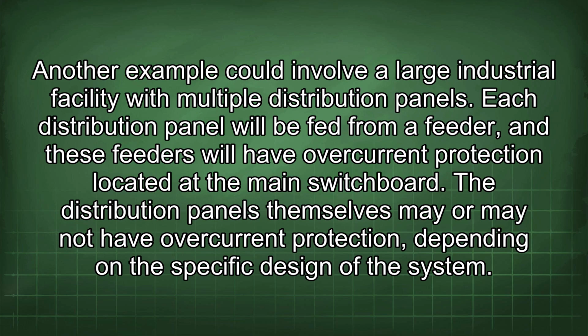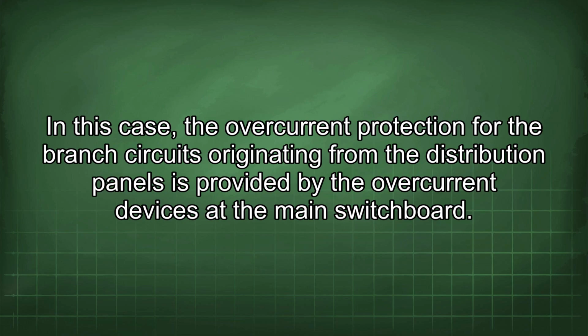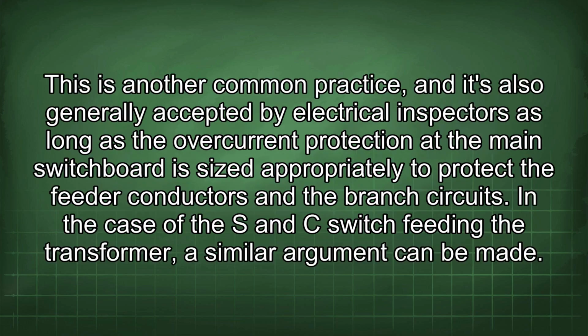Another example could involve a large industrial facility with multiple distribution panels. Each distribution panel will be fed from a feeder, and these feeders will have overcurrent protection located at the main switchboard. The distribution panels themselves may or may not have overcurrent protection, depending on the specific design of the system. In this case, the overcurrent protection for the branch circuits originating from the distribution panels is provided by the overcurrent devices at the main switchboard. This is another common practice, and it's also generally accepted by electrical inspectors as long as the overcurrent protection at the main switchboard is sized appropriately to protect the feeder conductors and the branch circuits.